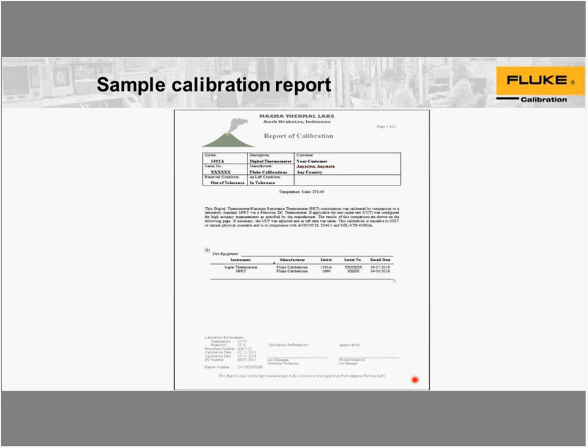It needs to be an actual definite pass to have the eligibility for auto sig. Otherwise, you have your calibrations technician. He signs it first, and that says the calibration is good from what he did. And we have somebody that comes through, signs it again, and as a double check, a second set of eyes, make sure the data is correct, make sure all the information up here is correct, because of the accuracy of the cert. This is the product that you're selling. Okay, you don't want to give somebody a bad product.